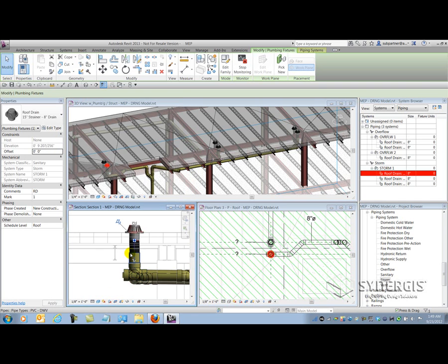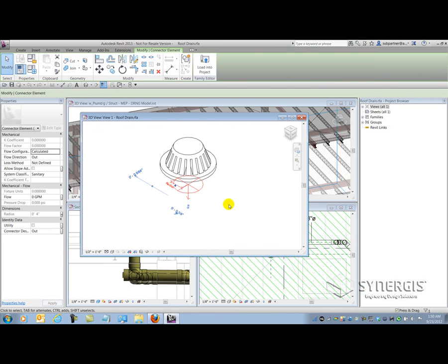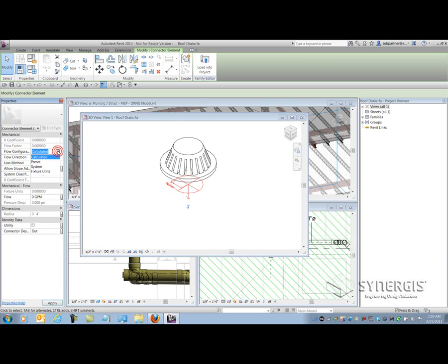Here's where we work around the problem. We select the roof drain and edit the family. In the family editor, I need to get to the connector — he's going to be the ultimate point of information for my coverage. Looking at his properties, he's set to the calculated flow configuration. What calculated means is it's going to aggregate downstream information at this point. But we're not aggregating — we want to input the information. So we don't need to be calculating; we need to be inputting the detail information.